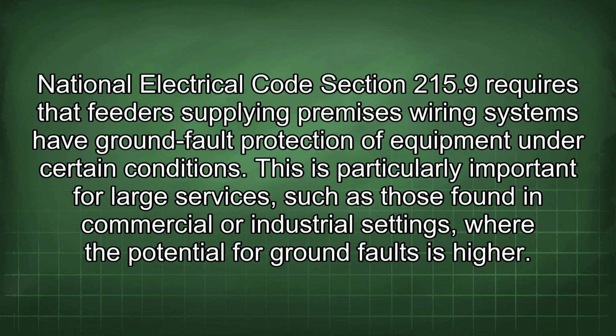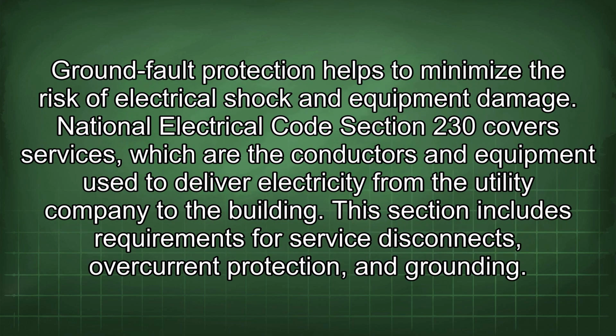National Electrical Code Section 215.9 requires that feeders supplying premises wiring systems have ground fault protection of equipment under certain conditions. This is particularly important for large services such as those found in commercial or industrial settings where the potential for ground faults is higher. Ground fault protection helps to minimize the risk of electrical shock and equipment damage.